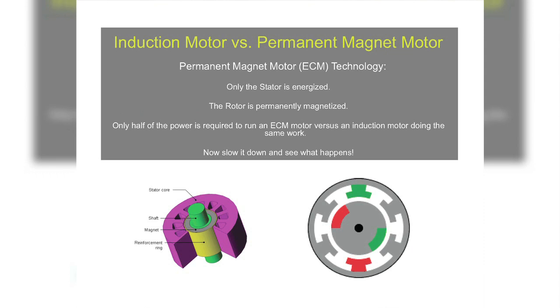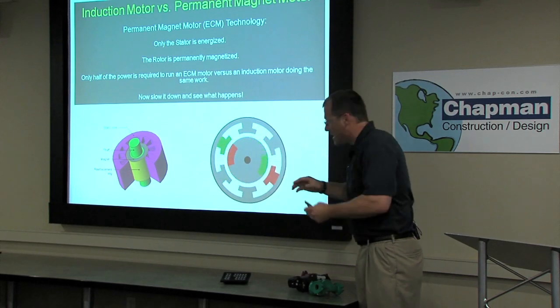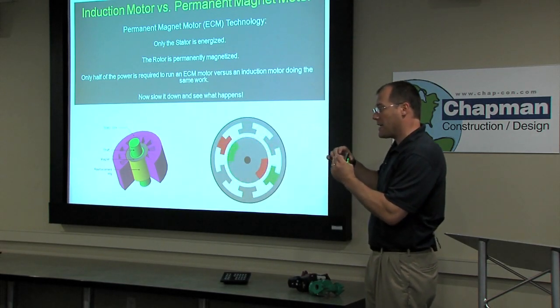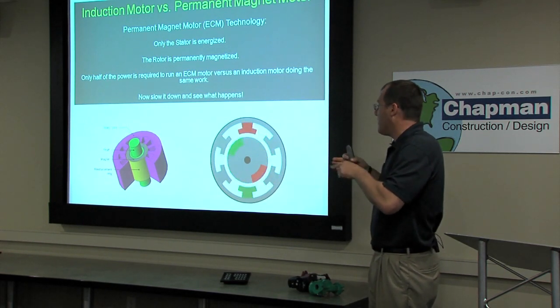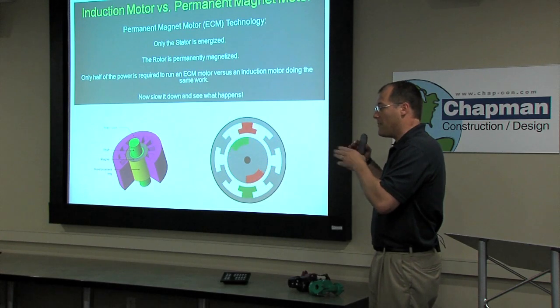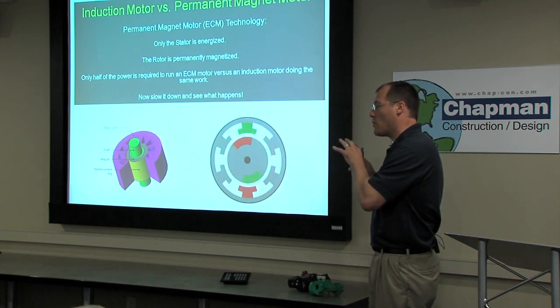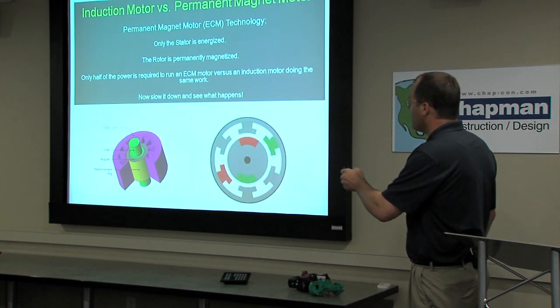So when people say, how does it work? You program this pump, let's say my building needs 30 feet of head pressure, differential pressure, to make the flow work in this building. You're going to program that in. It's then going to calculate based on where this is in relationship to this, and it's watching it all the time. If it's behind, it says, I've got to speed this up to get to where I calculate my duty point. So it adds wattage and speeds the shaft up. If it says now a bunch of zone valves just closed and I don't need as much flow, I'm getting ahead of the game, then it slows the watt input, lowers it, and the shaft slows down. And that's what's happening all the time in an ECM pump.